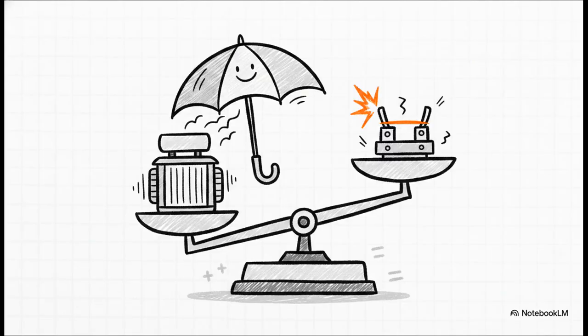This whole resistor philosophy is all about balancing 2 intensely competing needs. First off, it acts as that valve we talked about. It deliberately caps the fault current magnitude, which is absolutely crucial for protecting equipment from destructive forces and reducing those dangerous step and touch potentials for anyone nearby. But at the exact same time, it keeps the current just high enough to reliably trigger the protection relays. It's really just this perfectly calculated mathematical balance.